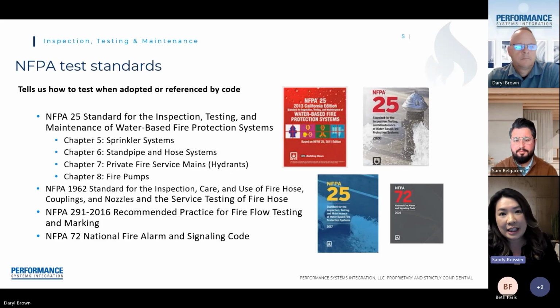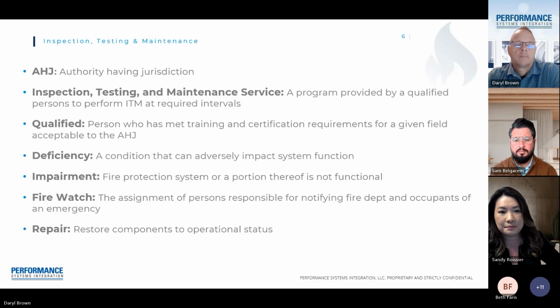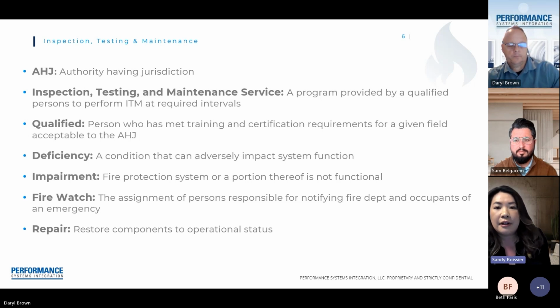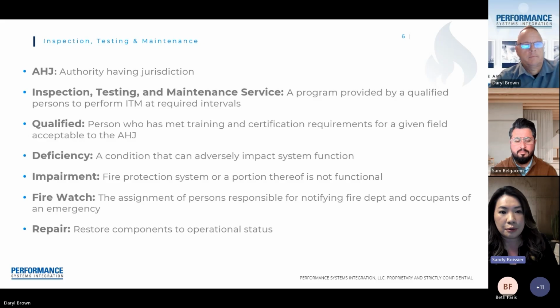The NFPA, known as the National Fire Protection Association, provides us with test standards that tell us how and when to test different types of fire protection systems. The ones we will be giving you a basic overview of are NFPA 25 for water-based fire protection systems and NFPA 72 for fire alarms. Some terms that you will come across regarding fire protection are AHJ, the authority having jurisdiction. They are the fire marshal or fire department in your local region that are responsible for enforcing code requirements. The AHJ can require that you provide more than what the code states, but they cannot require less.